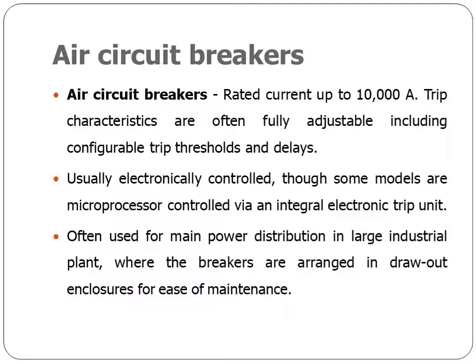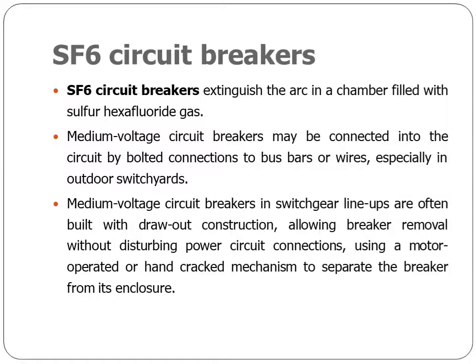Next one is air circuit breakers. Air circuit breakers are rated for current up to 10,000 amps. Trip characteristics are often fully adjustable, including configurable trip thresholds and delays. Usually electronically controlled in some models, or microprocessor controlled via an integral electronic trip unit, often used for main power distribution in large industrial plants, where the breakers are arranged in draw-out enclosures for ease of maintenance. SF6 circuit breaker. An SF6 circuit breaker extinguishes the arc in a chamber filled with sulfur hexafluoride gas. That is the name, sulfur hexafluoride.